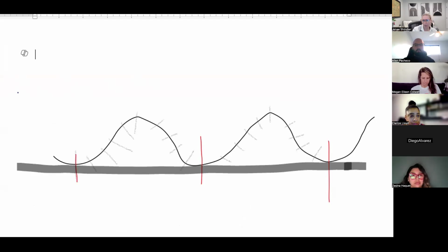is hopefully similar to what you see on the Linac, where you have your gating monitoring. Okay, this is a sine wave. It just means a wave that goes up and down in a cycle, according to breathing. So expiration, inspiration, expiration. This is 0. This is my baseline. At the end of the day, I would love it if everybody sat and their expiration was at 0, because that should be my 0 point.